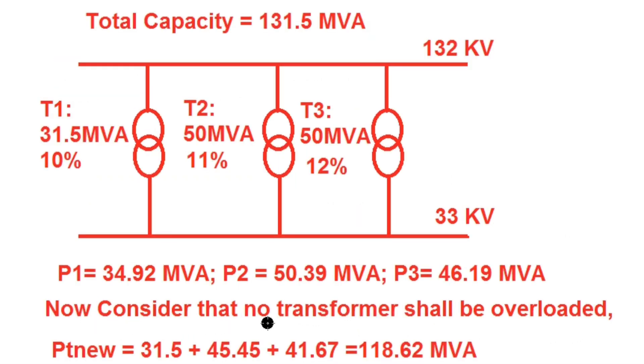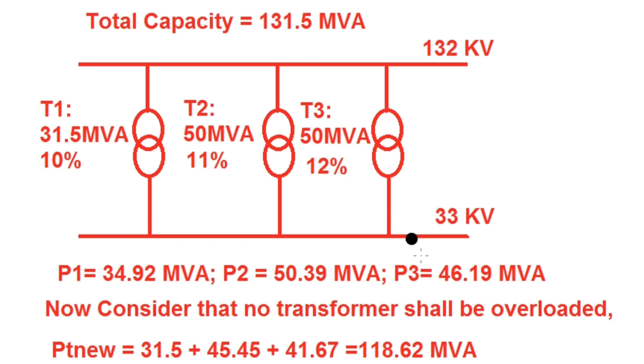Considering that no transformer shall be overloaded under parallel operation, the new usable capacity of the substation is 31.5 + 45.45 + 41.67 = 118.62 MVA. So out of a total installed capacity of 131.5 MVA, only 118.62 MVA can be utilized, because the transformers have different percentage impedances.